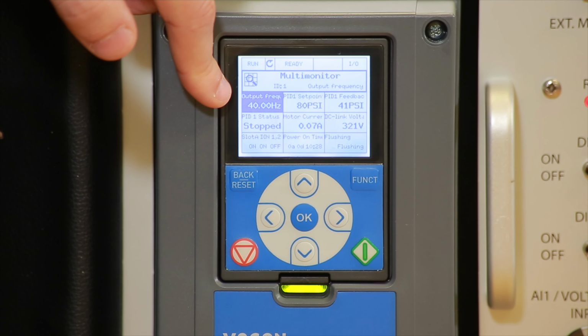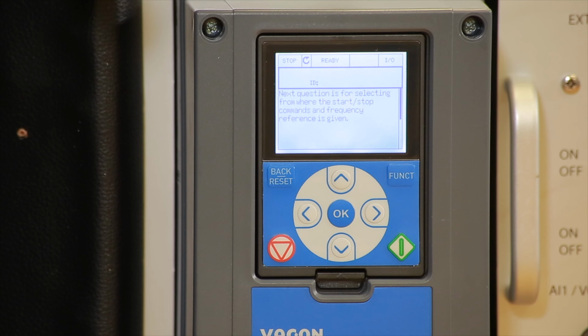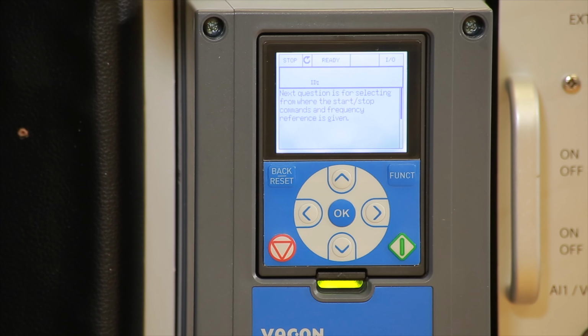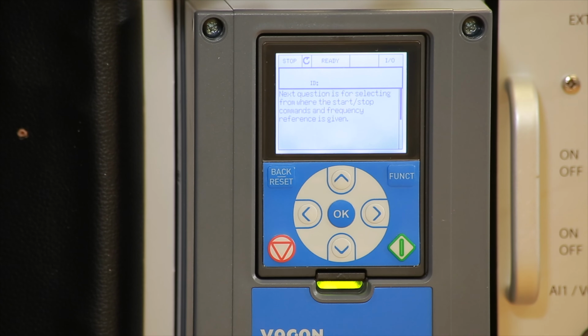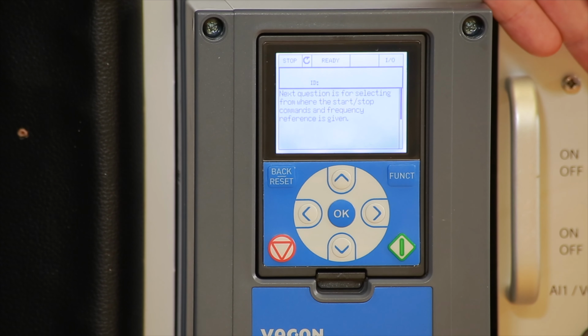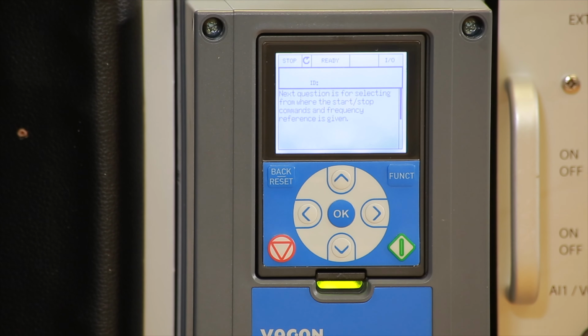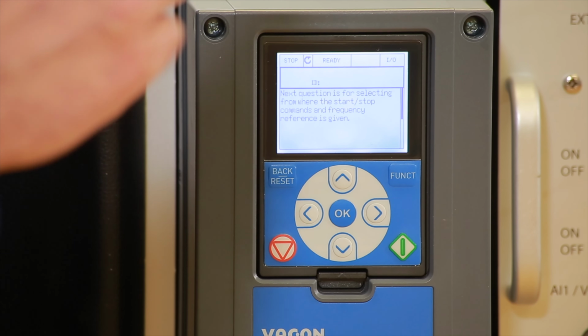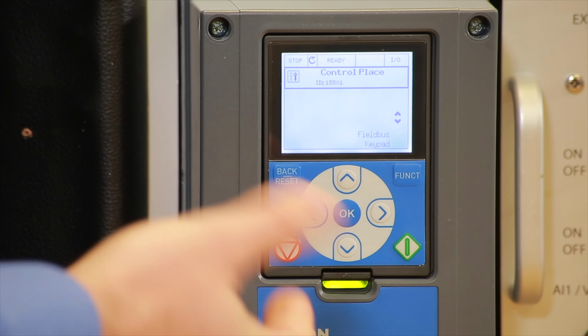Application wizard, always yes. Makes our life much, much easier when the drive is asking us what to do. So we'll click on yes, and the drive says the following. The next question is for selecting from where the start and stop command and frequency reference is given. So our drive has a potential of giving the option of a client to start and stop from the keypad, or from selector switches such as hand-off-autos, or from a communication protocol such as Ethernet or DeviceNet or any other protocol of communication that exists out there. So we're going to click OK, and we're going to select now what do we want.